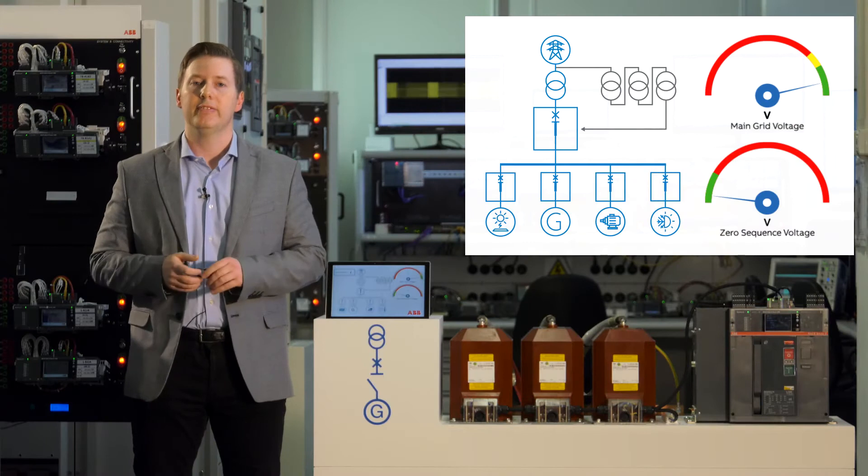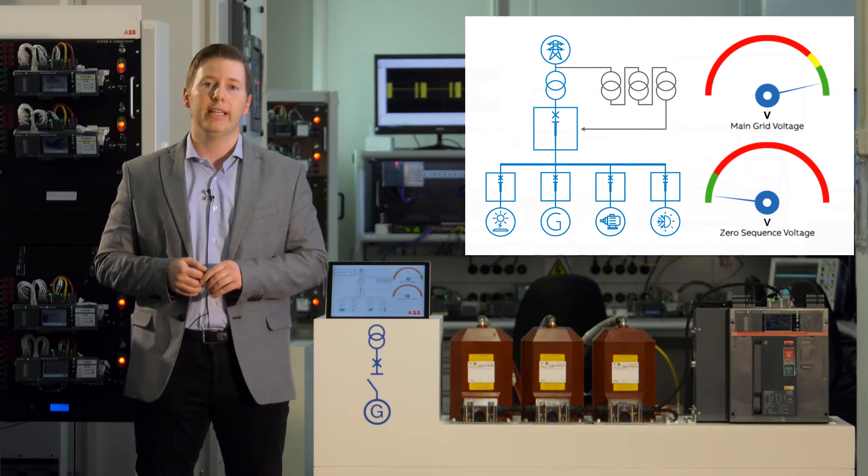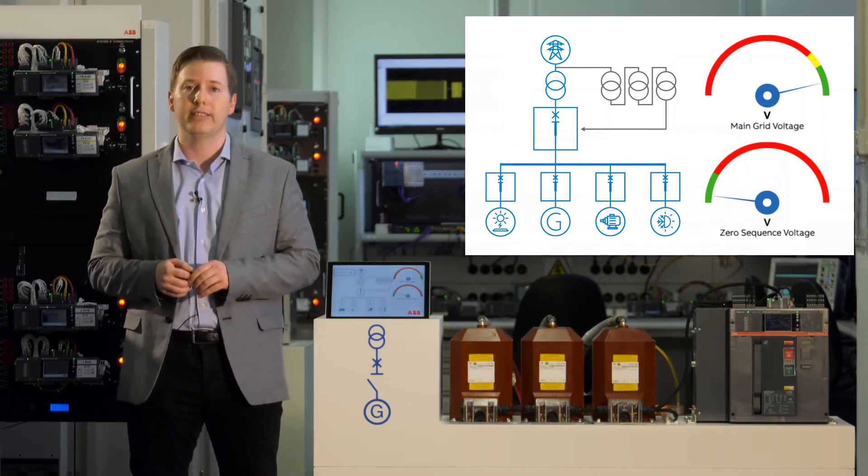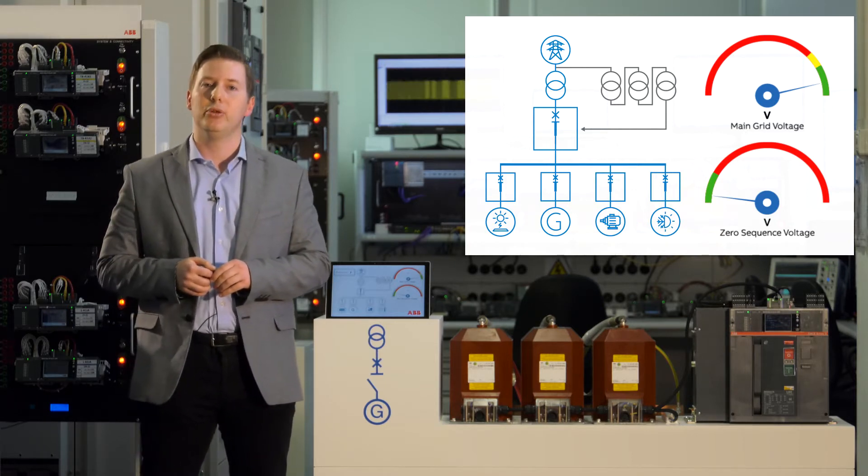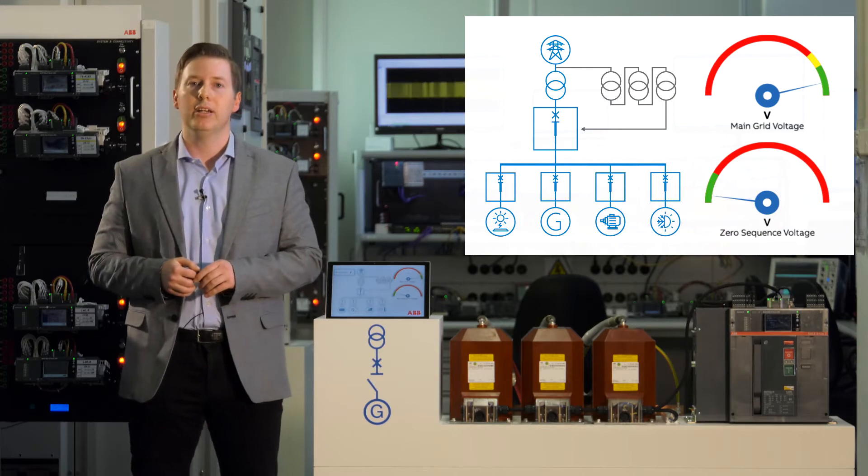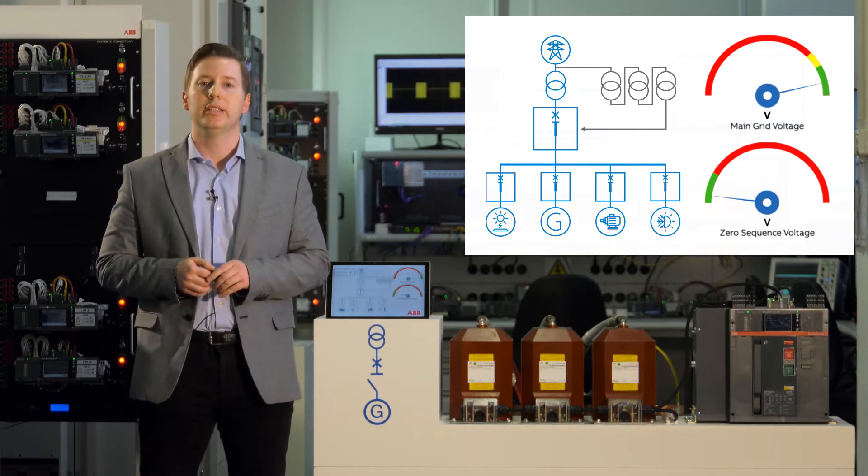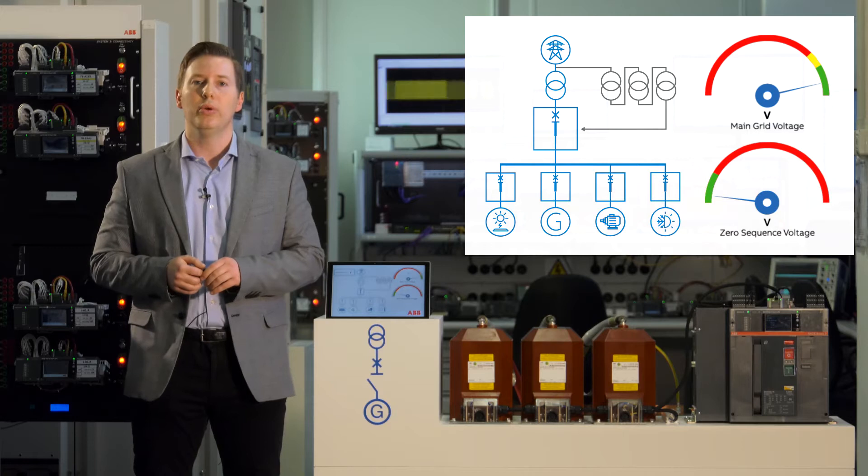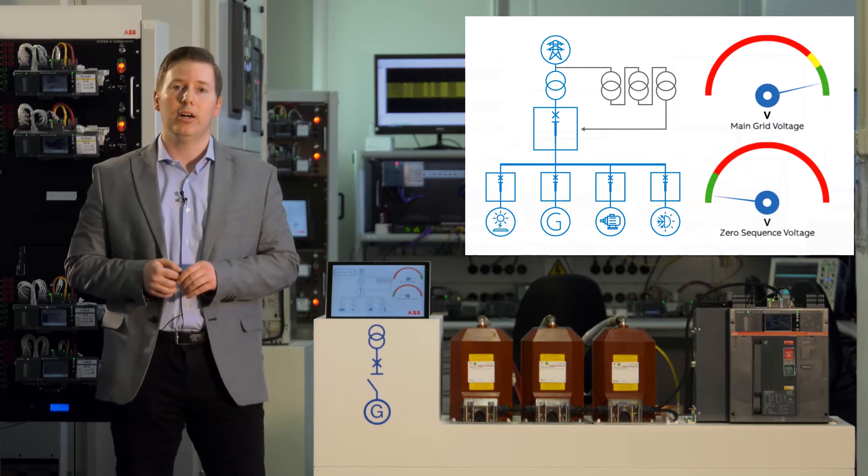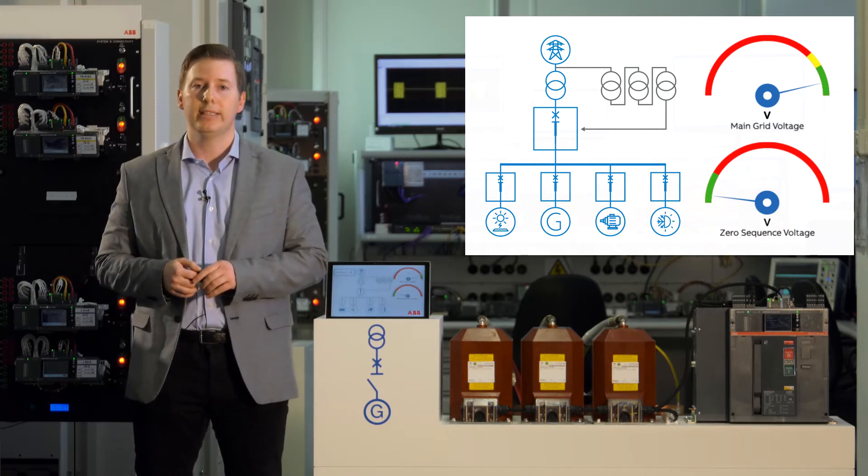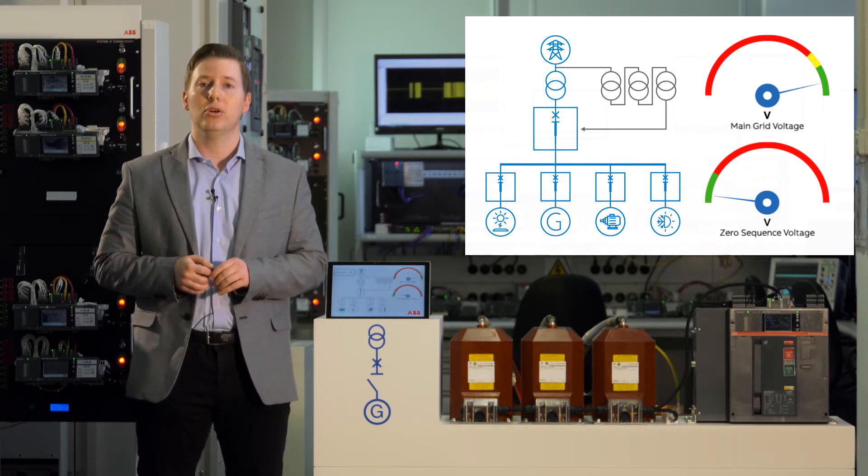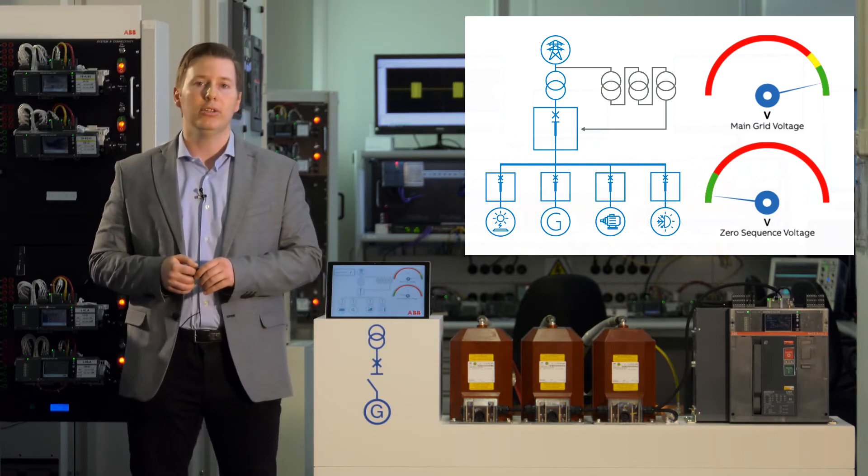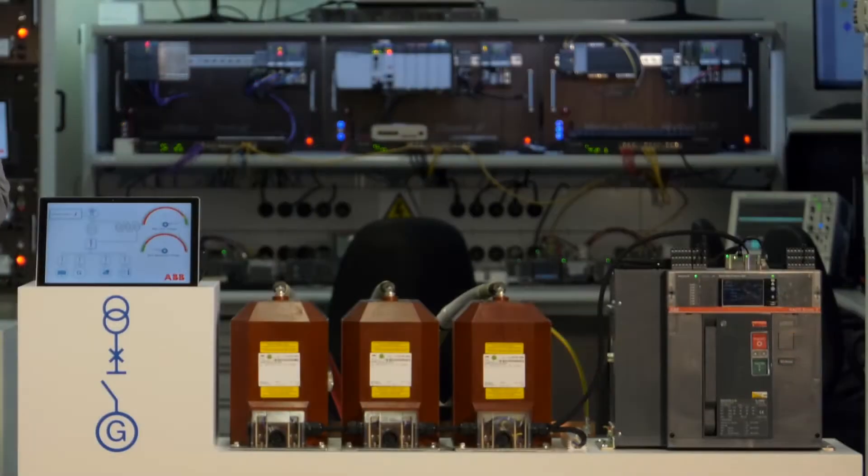This advanced feature is possible thanks to the implementation of several interface protections inside our Ekip Hi-Touch trip units installed directly on our EMAX2 circuit breaker. We have a complete set of under-over frequency and under-over voltage protections and the so-called vector shift in order to change automatically the frequency threshold.